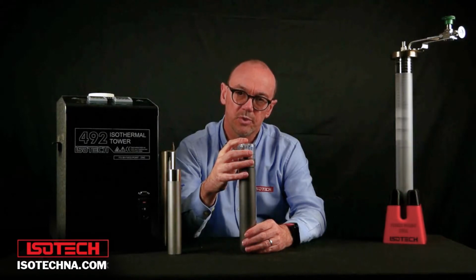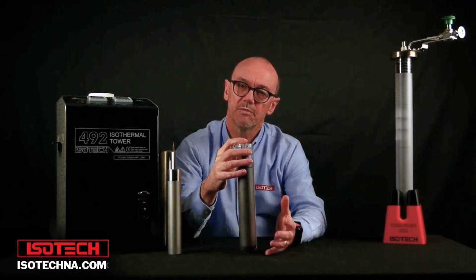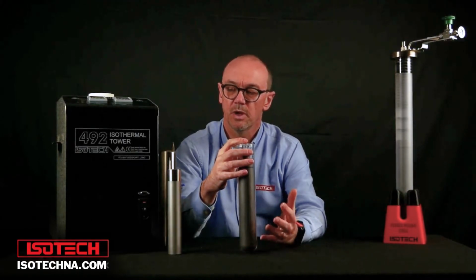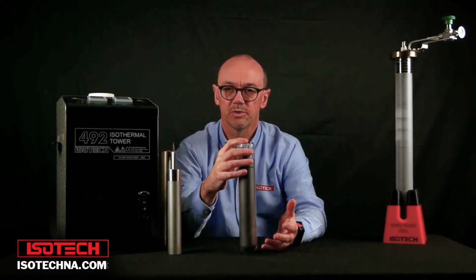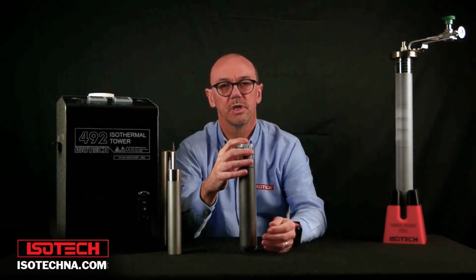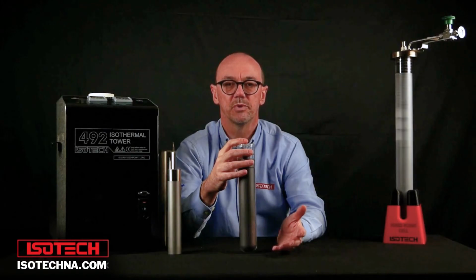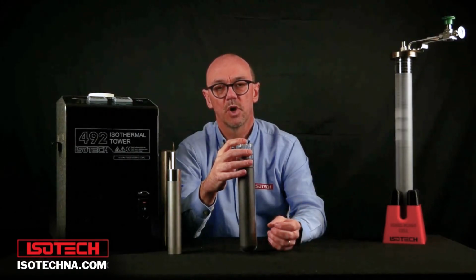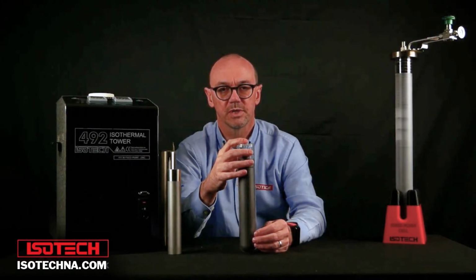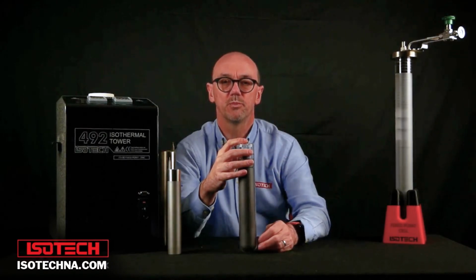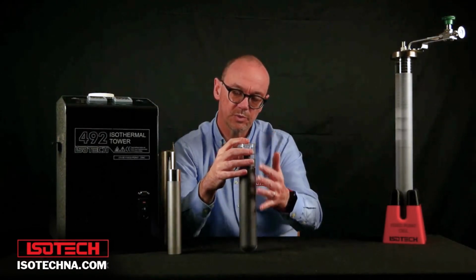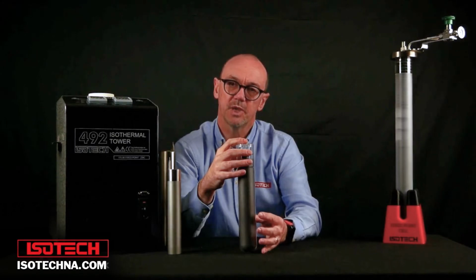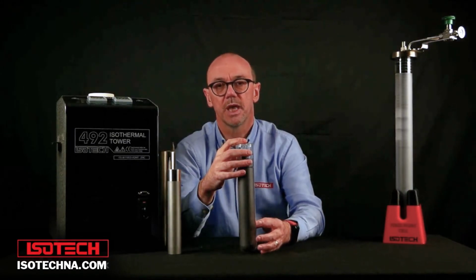With higher temperatures, the cells can have a finite life. So at lower temperatures, we've got cells in use for more than 30 years. But at higher temperatures, and at the copper point of 1084 degrees C, it's very close to the melting point of the glass. So if this was a copper cell, if the glass became spoilt, I'd have quite a headache.